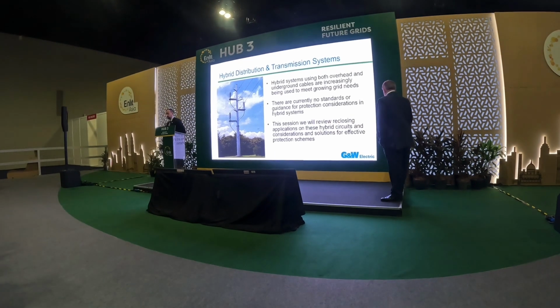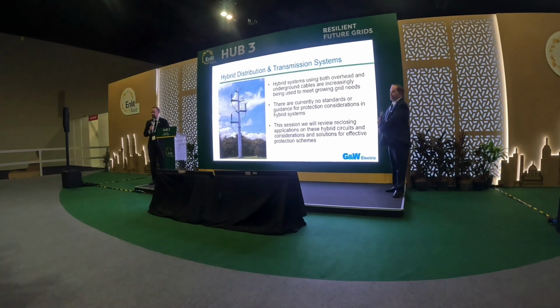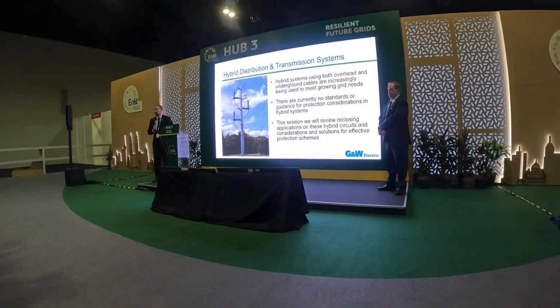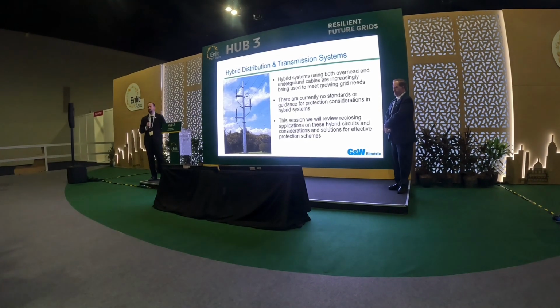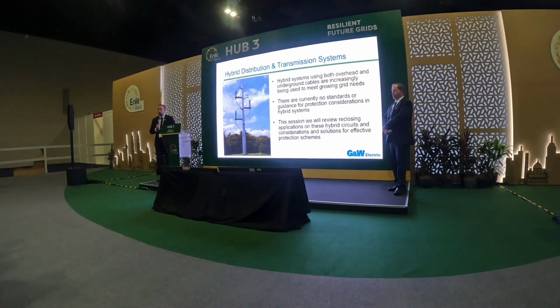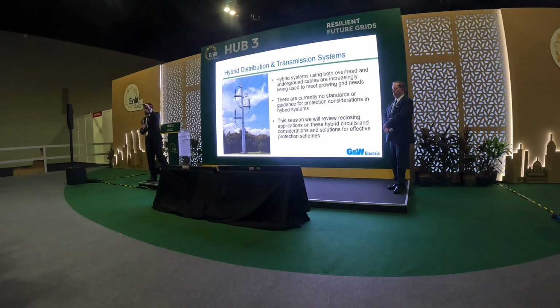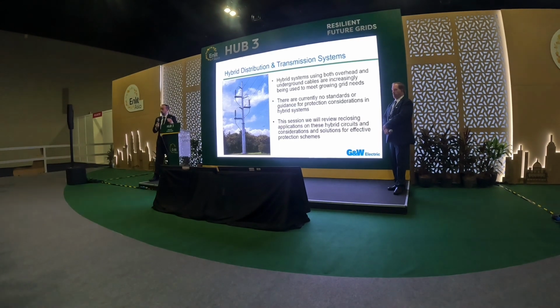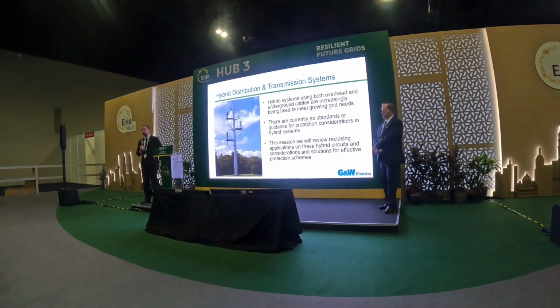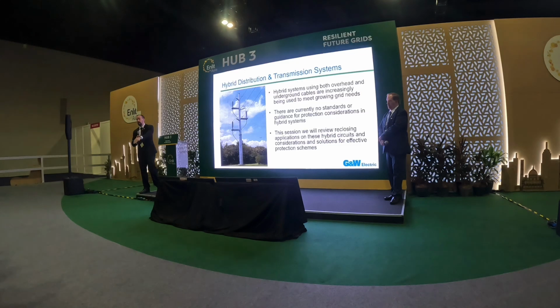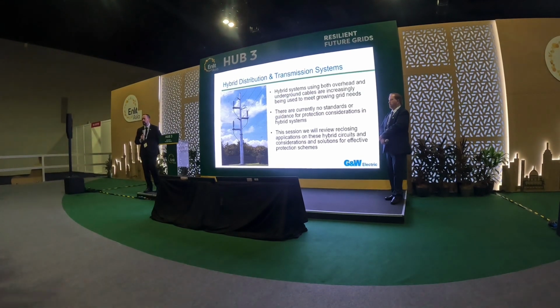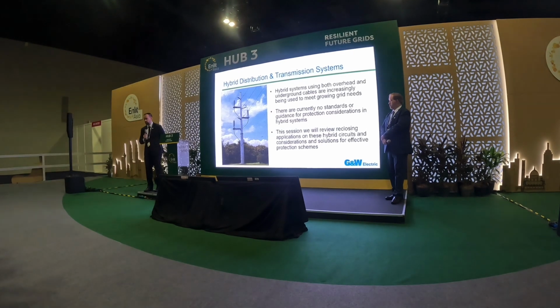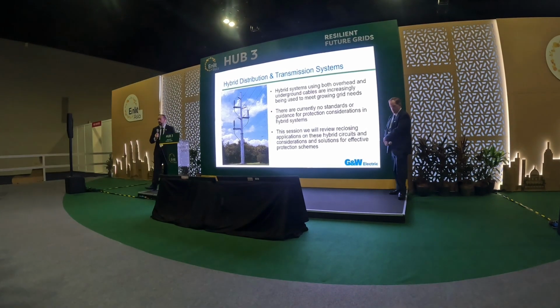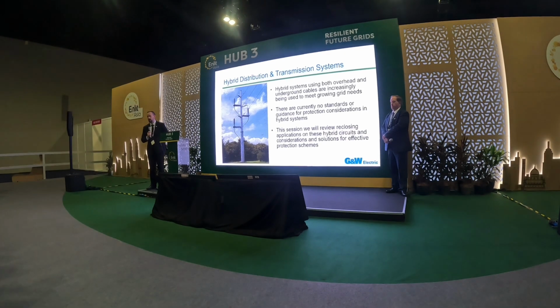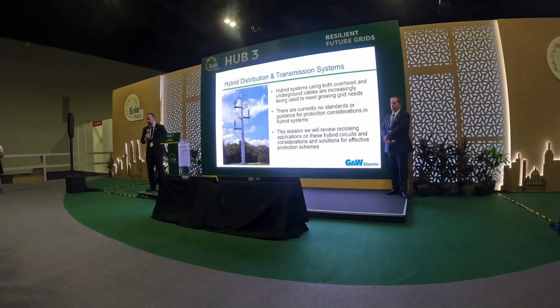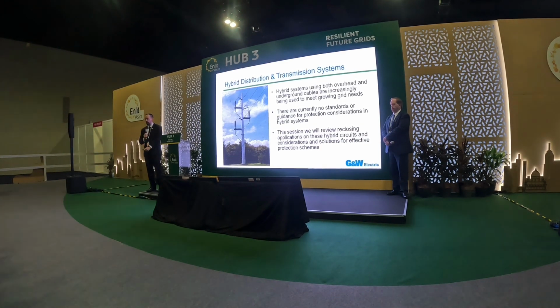So as Ron mentioned, we have seen an increase in the prevalence of our customers in both transmission and distribution level voltages transitioning their circuits from being either solely underground or solely overhead to systems that require you to transition at points on that same circuit. So maybe one piece is overhead fed, and then it transitions underground for a piece of that circuit. That does create some unique considerations from a protection standpoint, and that's really what we wanted to focus on today, specifically reclosing, a functionality that's very common on overhead systems, and the impacts on a system where you have both overhead and underground product.